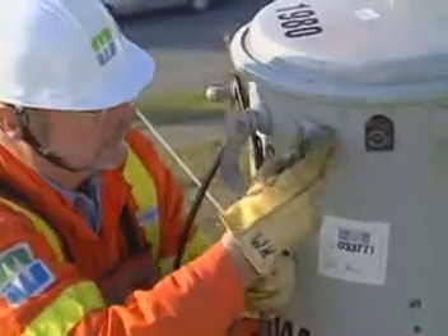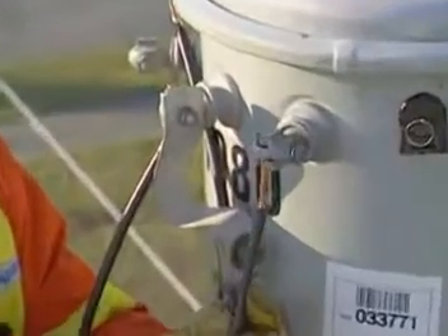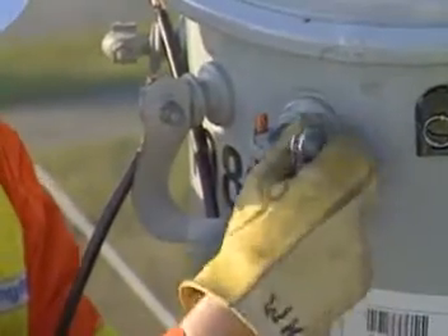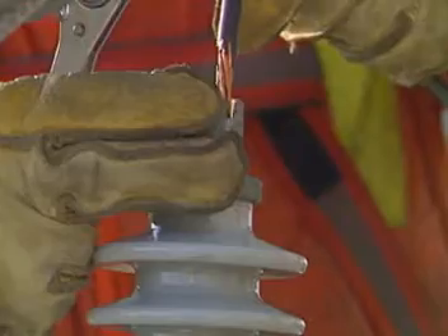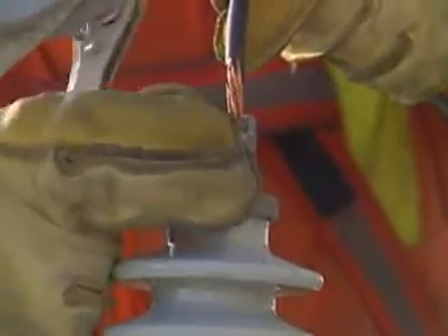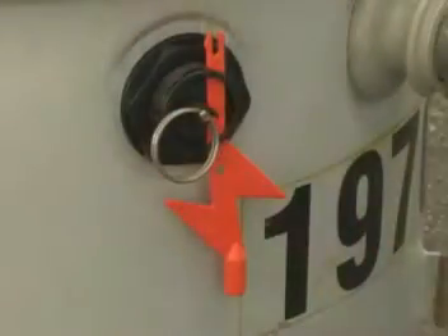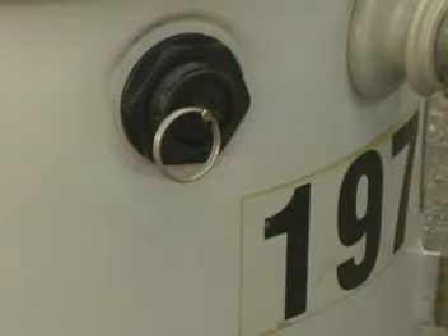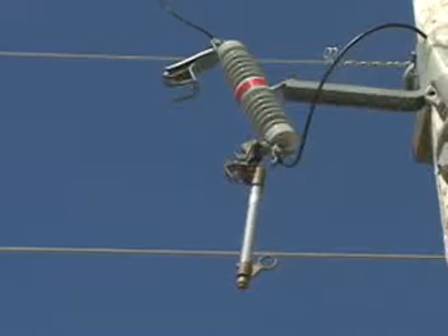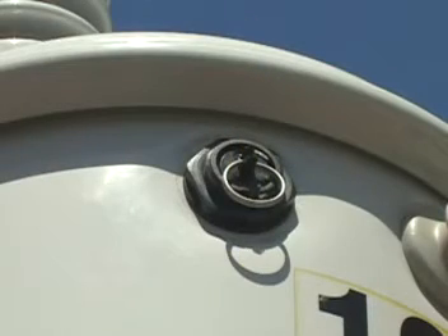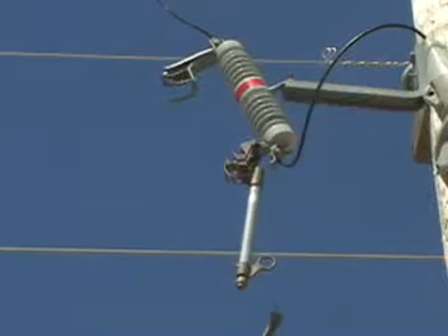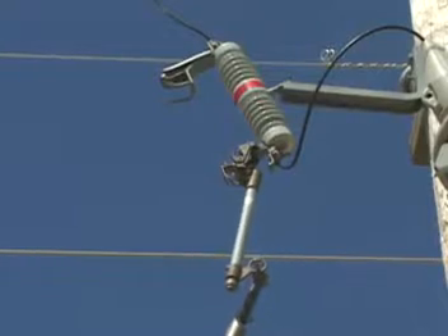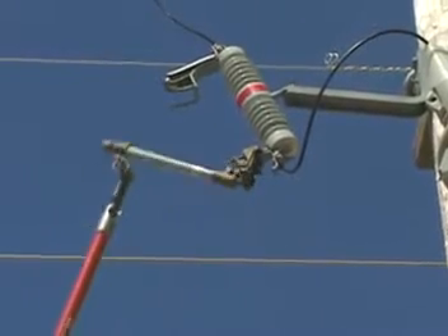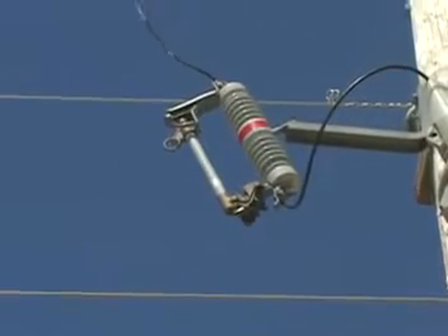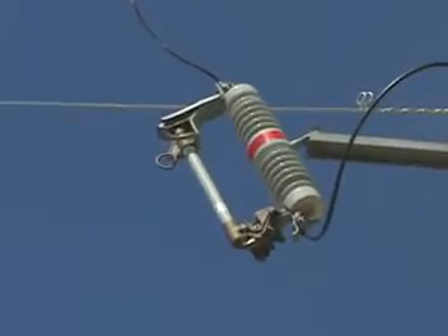Installing transformers with an IFD is no different than installing ones without an IFD. All the same fault checks and precautions must be made before energizing the transformer. The only difference in the installation process is the removal of the shipping lock once the transformer is mounted. If the fuse cutout is open, but the IFD has not been activated, chances are the transformer is okay to re-energize, providing all normal fault checks are done. Nothing can be considered 100% when it comes to safety.